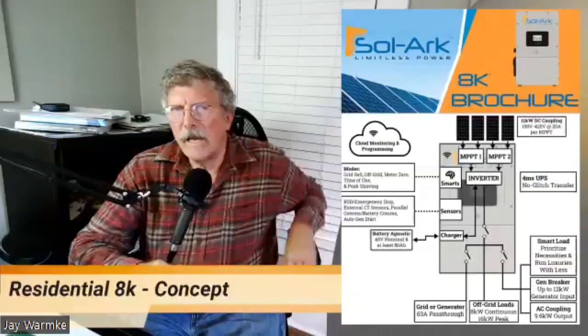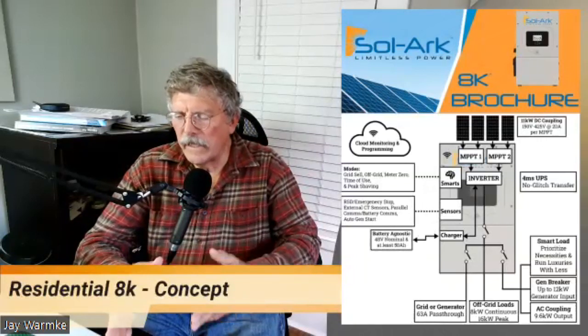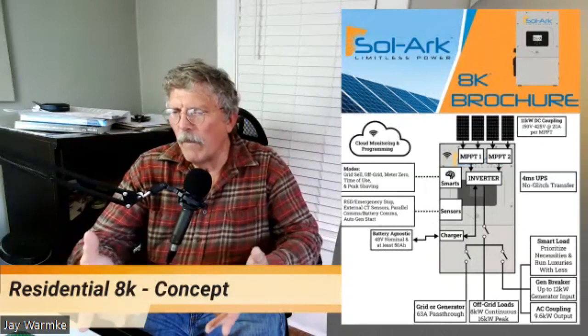Then you end up putting switches outside still. Right. But it was nice from the standpoint of having built-in breakers and having everything self-contained. Yeah, I know that typically they do require the AC disconnect to be located within 10 feet of the meter, externally operable, clearly marked.